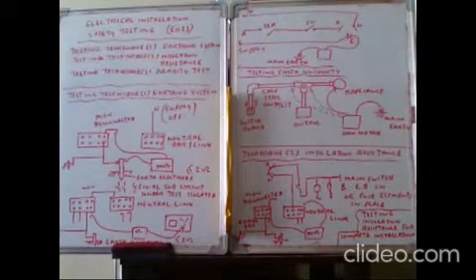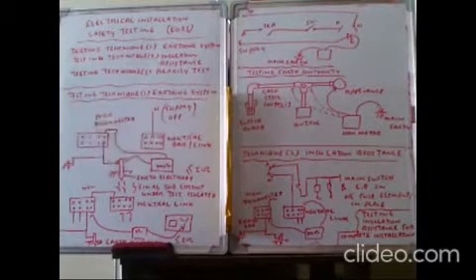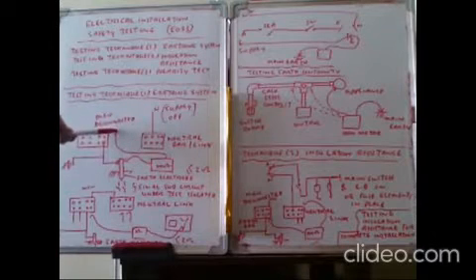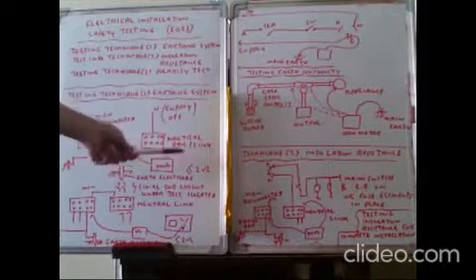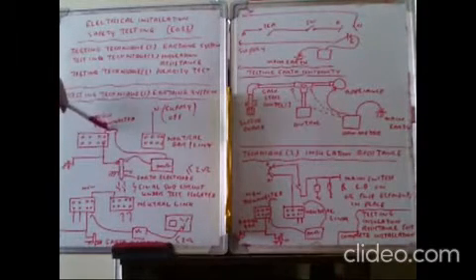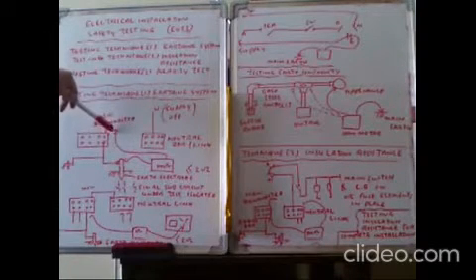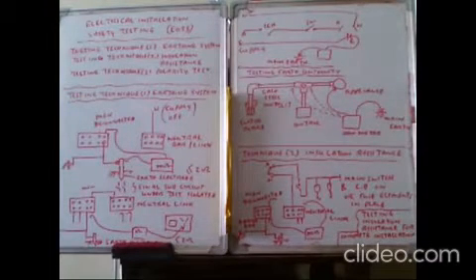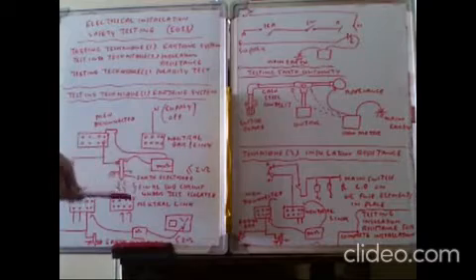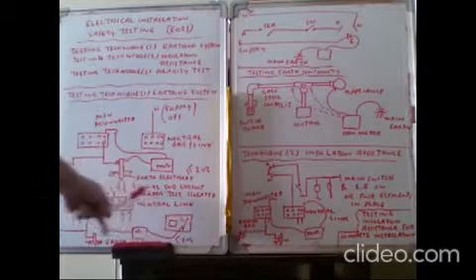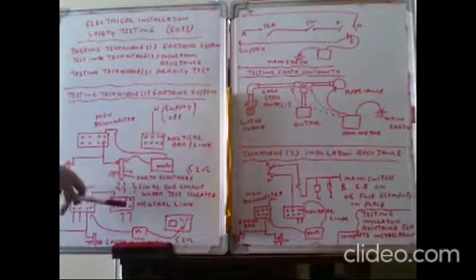Switch off the supply and take out all wires connected to the neutral wire. Connect the ohmmeter — one terminal to the neutral, another terminal to the earth link terminal. The resistance must be less than 2 Ω. For testing the active wire earth path, connect the ohmmeter from the active wire to the earth connection link; resistance must also be less than 2 Ω. Also test the socket outlet earthing: switch off supply, isolate the supply, and remove the neutral link.